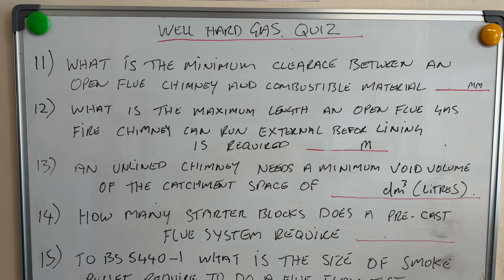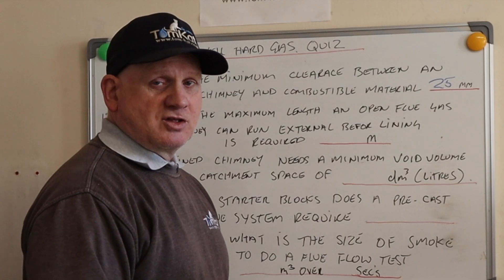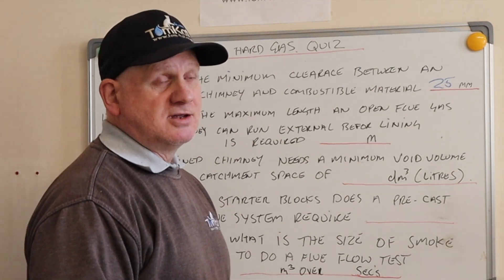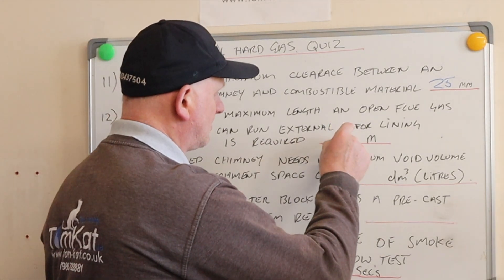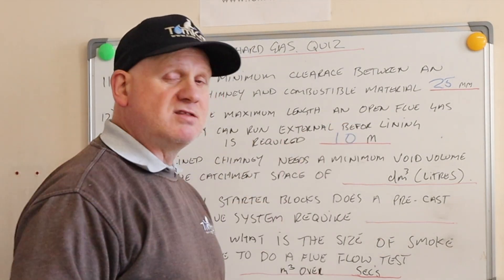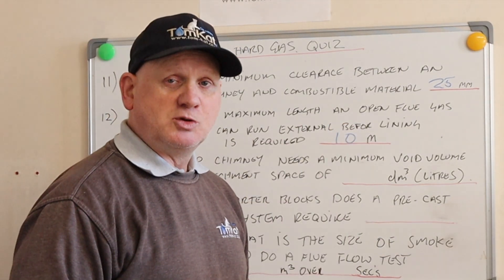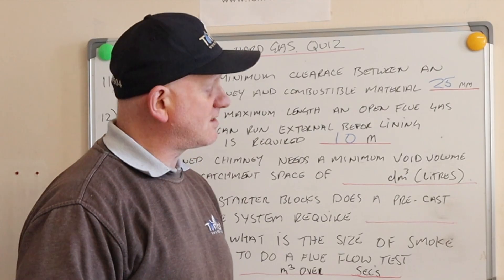Question number twelve: what is the maximum length an open flue gas fire chimney can run external before lining is required? If you said 10 meters, you would be correct.